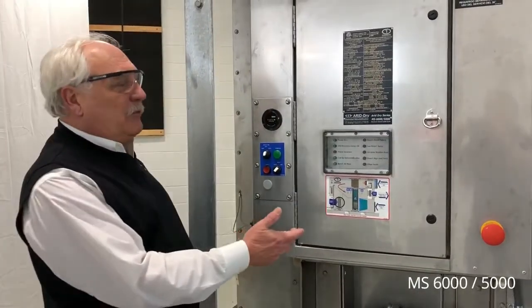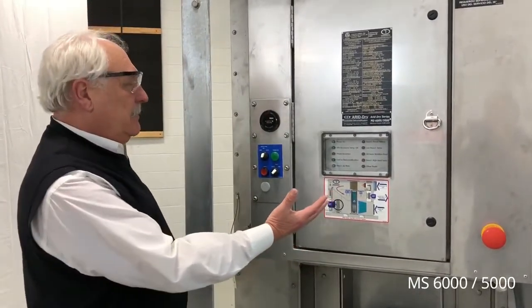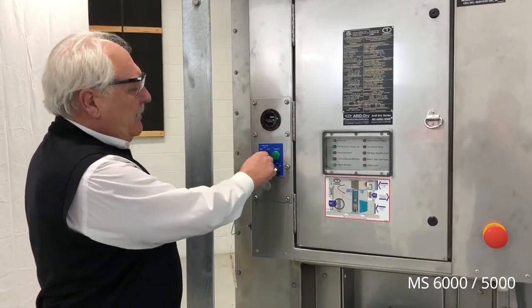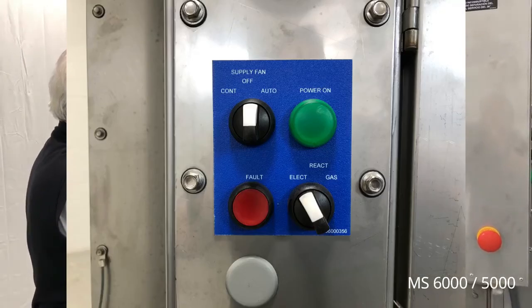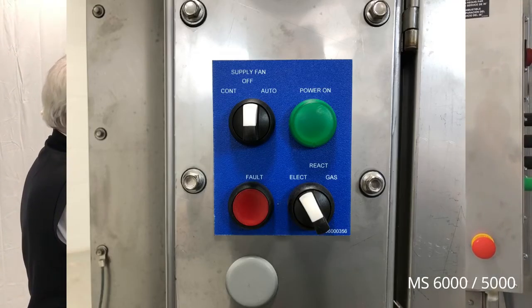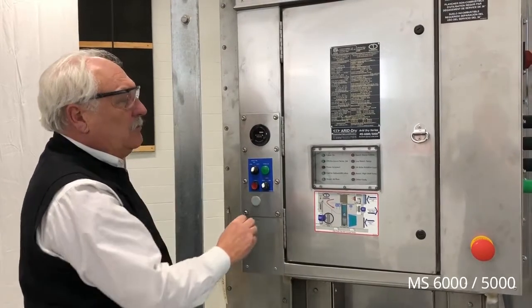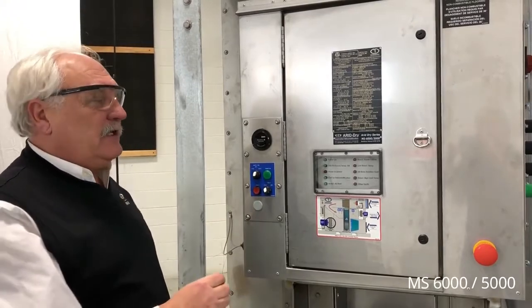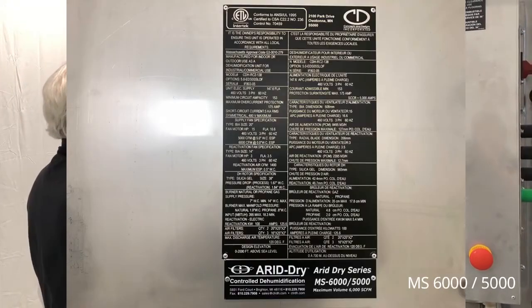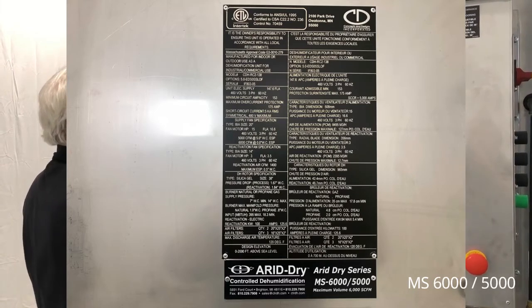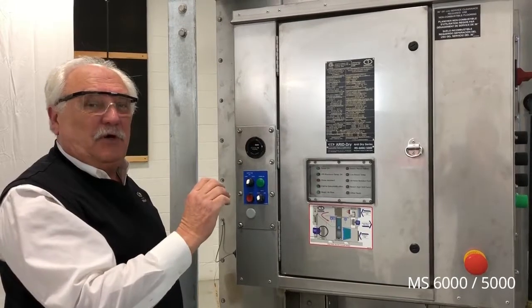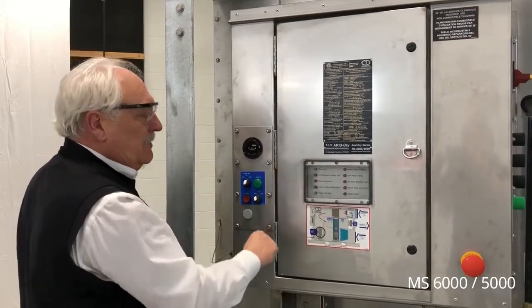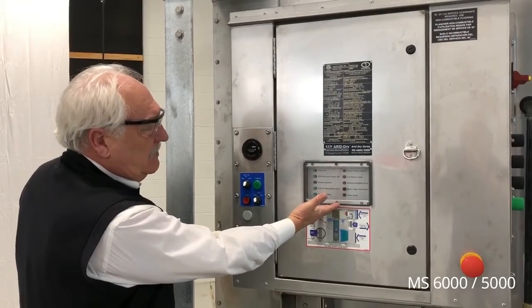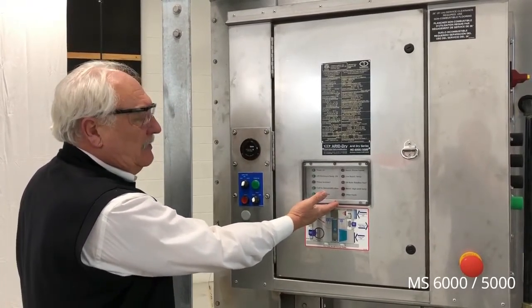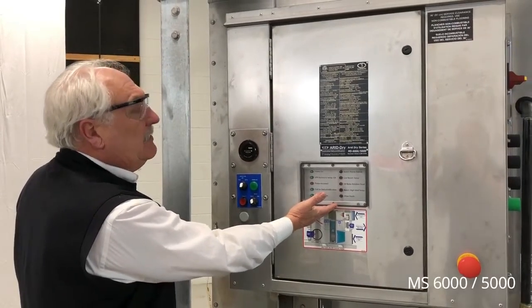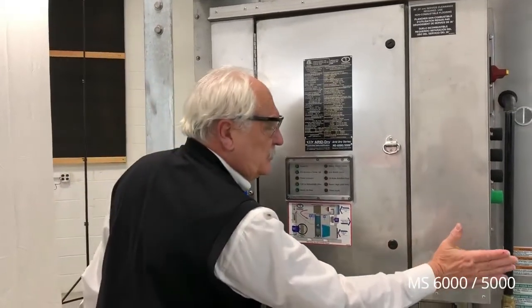The unit controls for operation are located in a low voltage panel on the end of the unit. Here we find an hour meter, the supply fan and unit auto or continuous on-off, and then we can select our reactivation means, either gas or electric, so the unit knows which reactivation source to use to reactivate the desiccant. We also have a full specification nameplate, including a serial number that is required for all parts or service as the unit ages. On the door we have a window that shows our indicating lights. Red are usually indicating a fault and green are indicating things are okay. Further on this panel is our emergency stop.